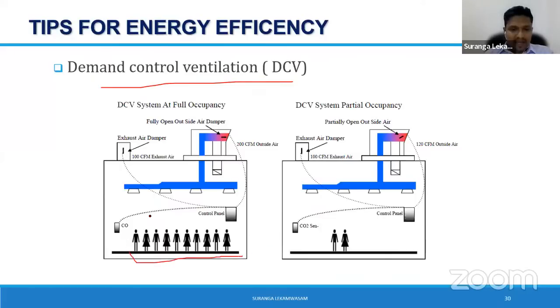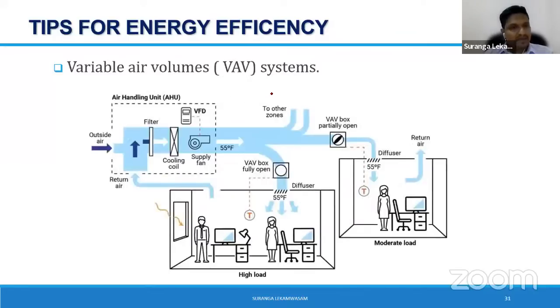Let's say now I have designed the system for 100 pax, but now it is at part load. I have, let's say, 10 pax. If I dump the same amount of fresh air, it is an energy wastage. So I control the fresh air amount based on my CO2 level. It's a matter of adding a CO2 sensor and controlling my blower or the damper with a small control. So you can vary the supply fresh air amount according to the demand. So DCV, or demand control ventilation, is very smart in terms of energy efficiency.